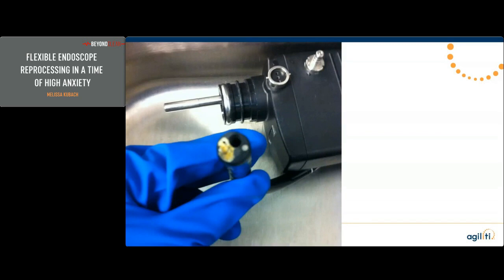There are times where blood or debris can actually get baked onto those light guide lenses, especially if it's a long procedure and you're using a xenon light source—it can get hot. So you really want to pay attention to those when you're cleaning. Not just that they're not chipped, but really look for any kind of residual that's stuck or baked on there that might be very difficult to get off.